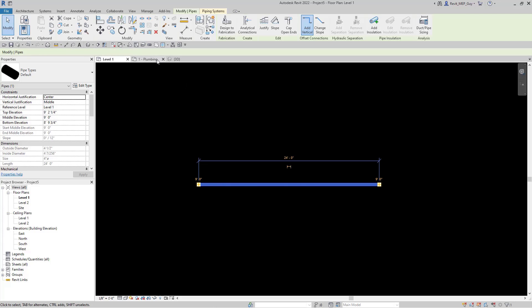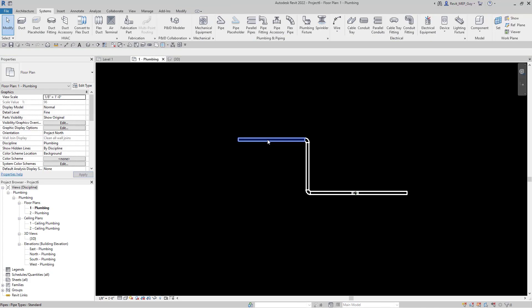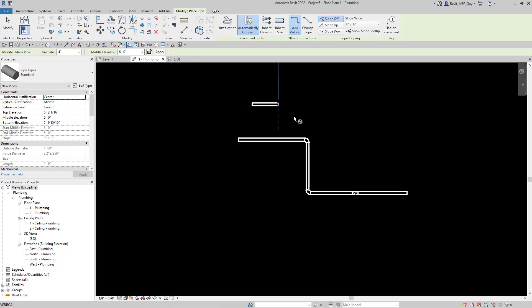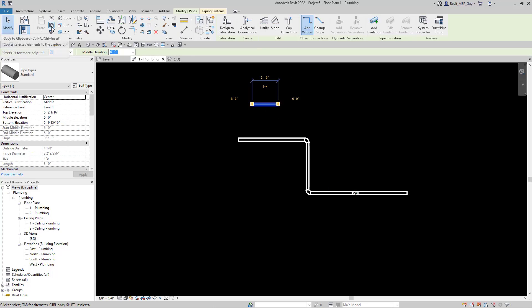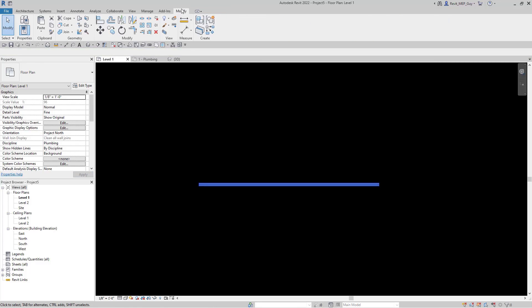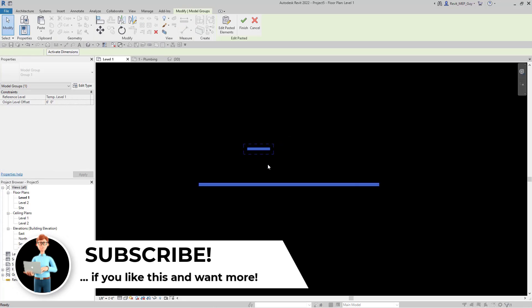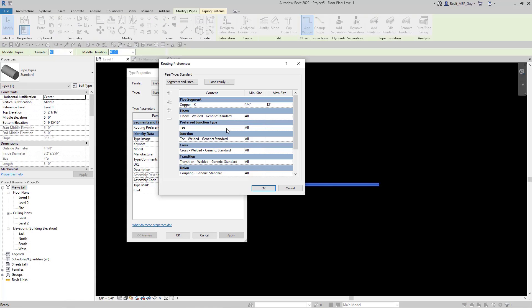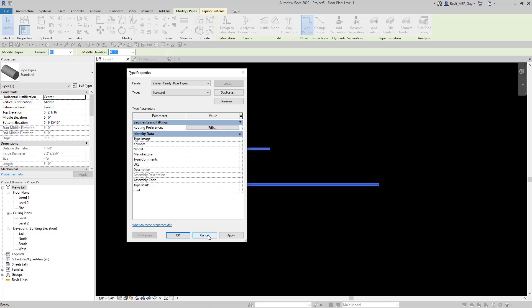I'll hit Cancel and go back to our plumbing project. I'm going to select one of these pieces of pipe — just a small piece of pipe — select it, and copy it to the clipboard. Now I'll go to my architectural project and paste this piece of pipe into this project — I'll just paste it anywhere. Now if you click on this piece of pipe that I just pasted in, click Edit Type, hit Edit under Routing Preferences — as you can see, all of my fittings have been loaded into this architectural project.